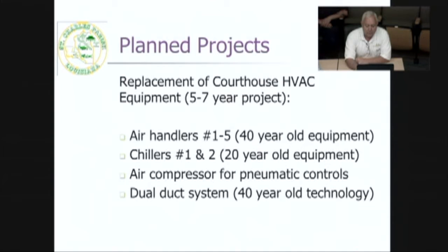We're looking at changing from pneumatic controls for the ACs and HVAC equipment to electronic and digital. We have a dual duct system in the courthouse, which is very old technology, probably about two generations ago, where depending on what temperature you want the room, you either dump more hot air than cold air or vice versa.